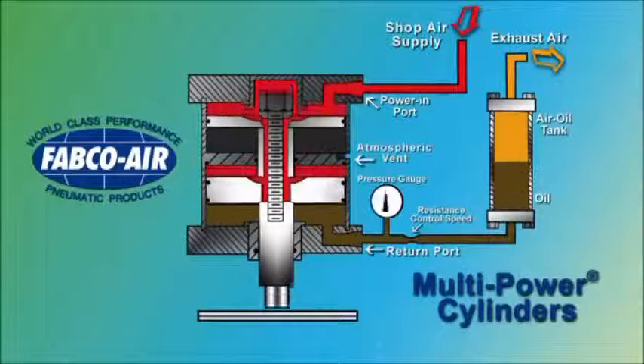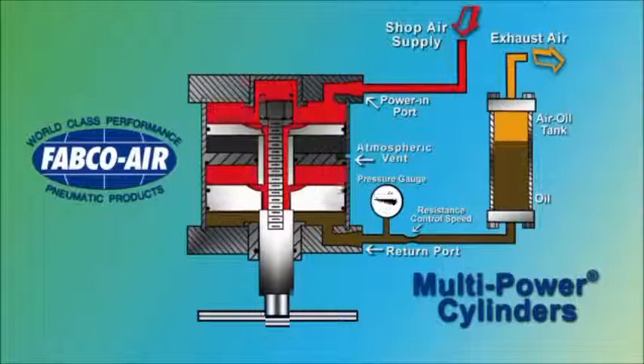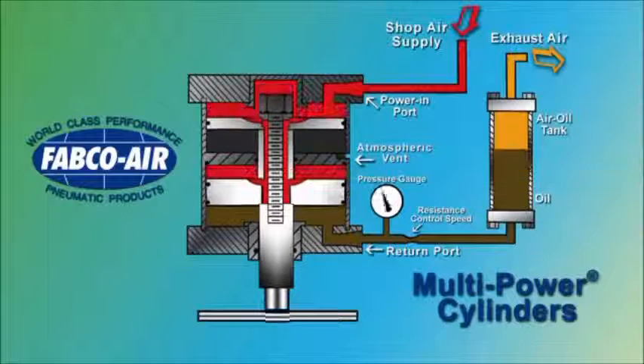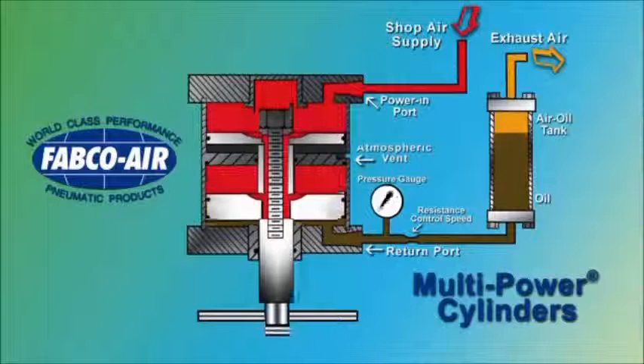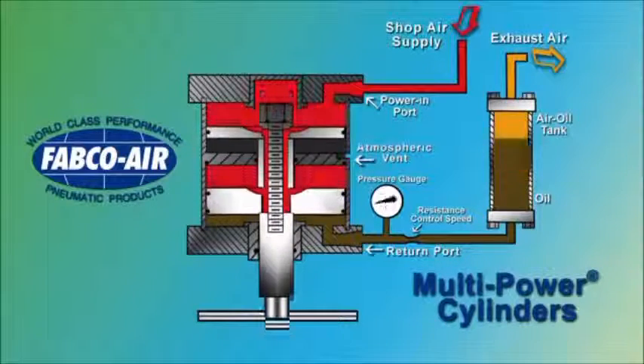To capture these potentially destructive forces, Fabco Air offers a hydraulic shock and speed control option. Oil from an air-oil tank is used for the return medium. This oil passes through a resistance, such as a flow control, which provides speed control of the cylinder.